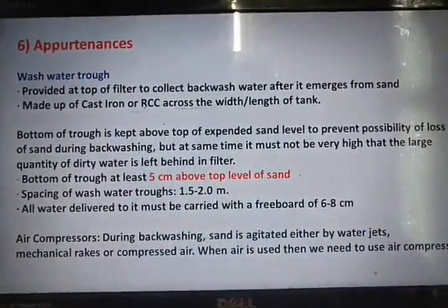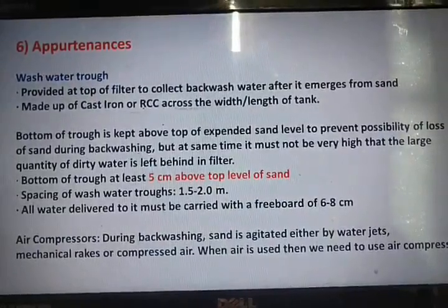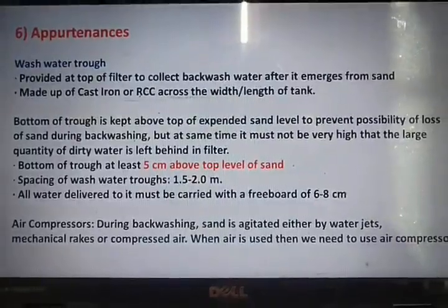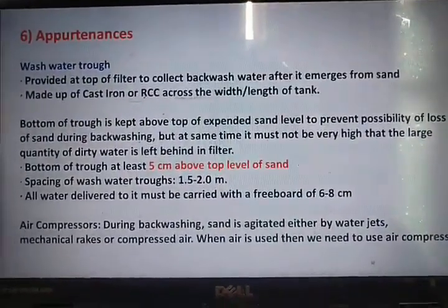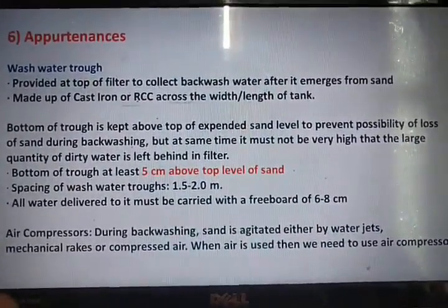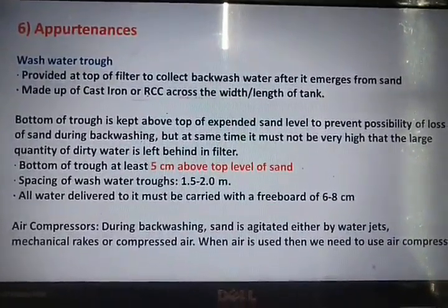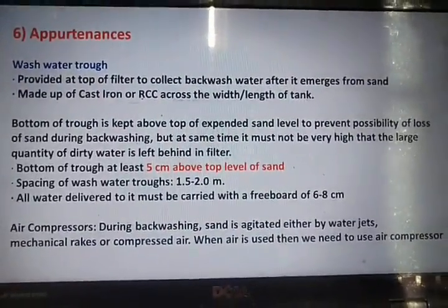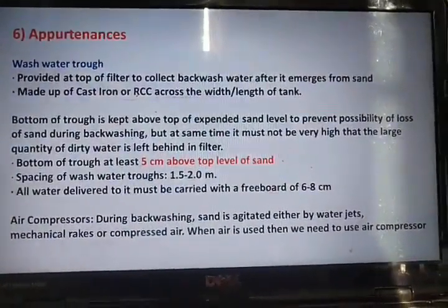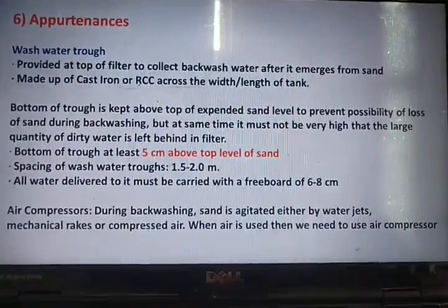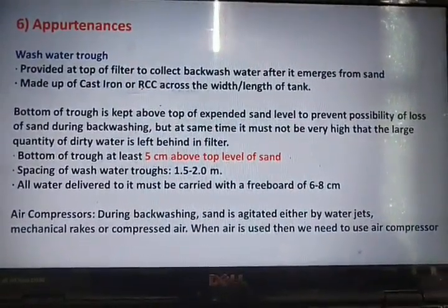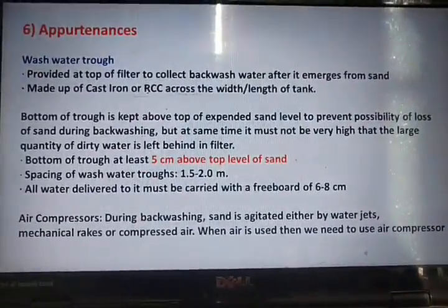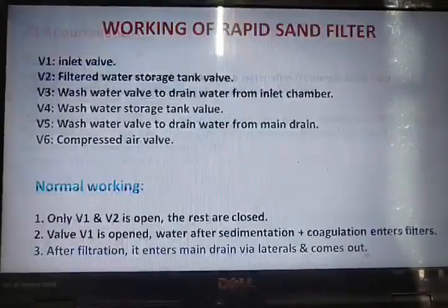During backwashing, the sand is agitated by water jets, mechanical rakes, or compressed air. When air is used, we need to use the air compressor. That is, during backwashing, before letting the water into the filter, we'll use the compressed air to clean the sand. I'll show you all these appurtenances during the backwashing, so that you will come to know their location and uses.